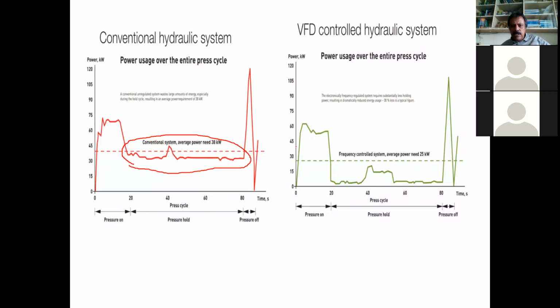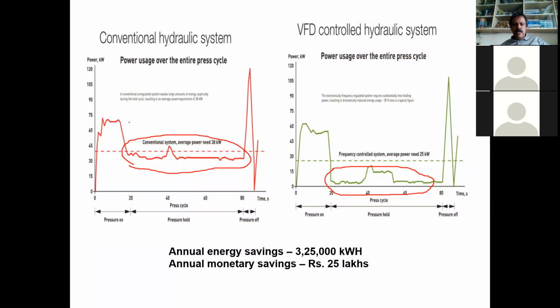After providing the VFD, the initial peak was there anyway for the various operations, pushing and pointing. Then, when there is no need, we have reduced the speed of the hydraulic motor. So you can see the power has drastically declined here in this idle period compared to this. Then, of course, you have the peak. Using a pressure controller with the VFD, when the valve opens, the pressure drops, and immediately the VFD picks up the speed to provide the necessary pressure for the hydraulic circuit.